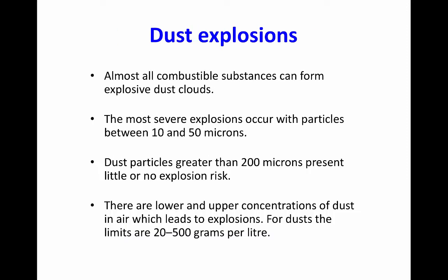Dust explosions. Almost all combustible substances can form explosive dust clouds. The size of the dust particles is important in determining whether an explosion will occur or not, and how severe it will be. The most severe explosions occur with particles between 10 and 50 microns. Dust particles greater than 200 microns present little or no explosion risk.